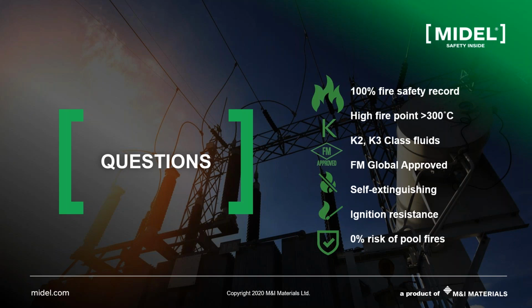Yes, as I mentioned in the presentation, best practice is you need to identify them separately. Some utilities paint their transformers with esters either green or blue. I think in South Africa they are painting them blue, or adding another plate near the nameplate of the transformer, which indicates clearly that this is retrofilled, say, or filled with an ester. This is the type, MIDEL 7131, say. Otherwise, you will end up at risk of contamination. Though, I would say, even with contamination, we don't expect failures. The only side effect is a reduction in the fire point.